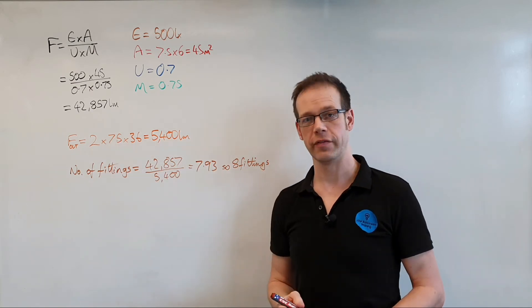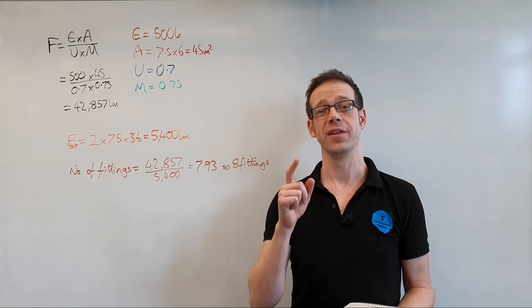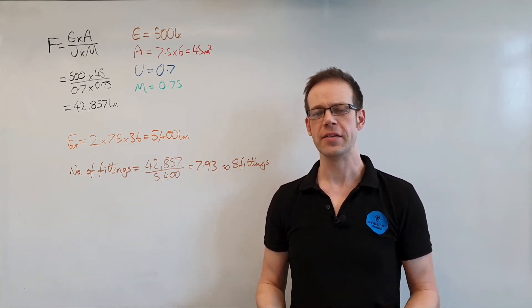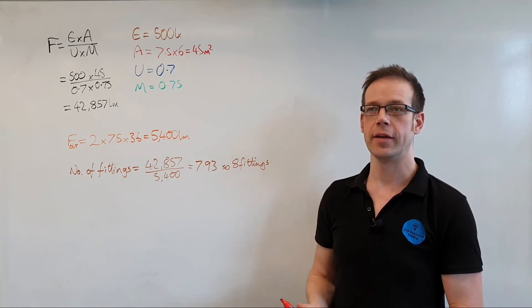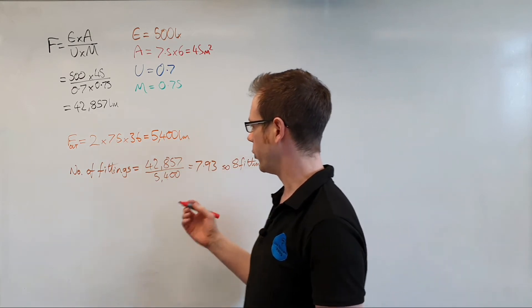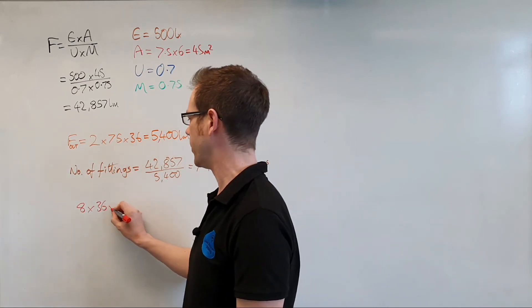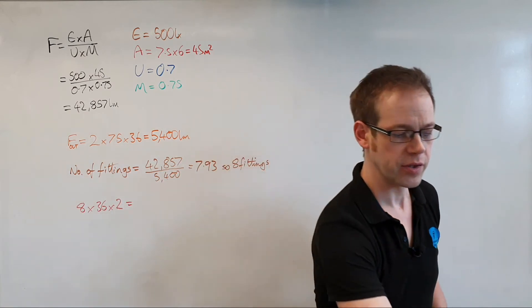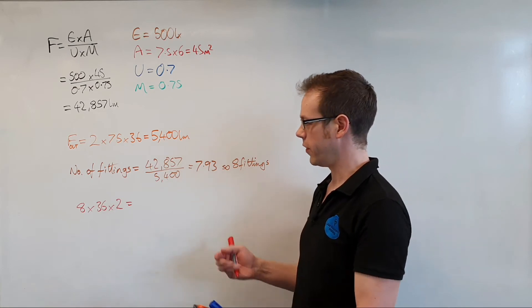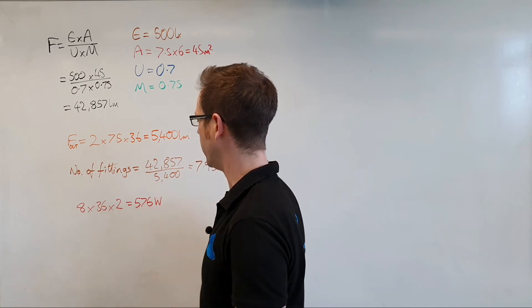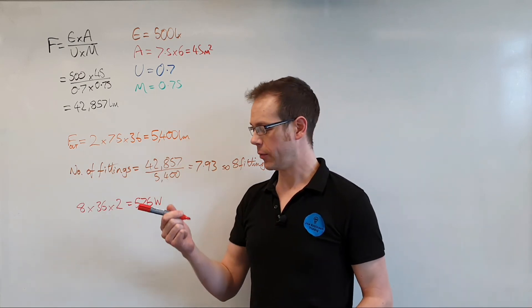We've answered the first part of the question — we need eight light fittings. The next part asks how much current those fittings will draw. First we find the total power: eight fittings, times 36 watts per tube, times two tubes, gives us 576 watts. So this lighting circuit will dissipate 576 watts.